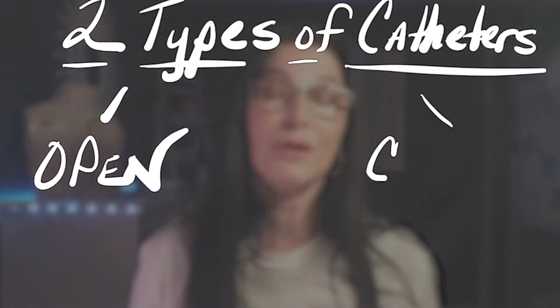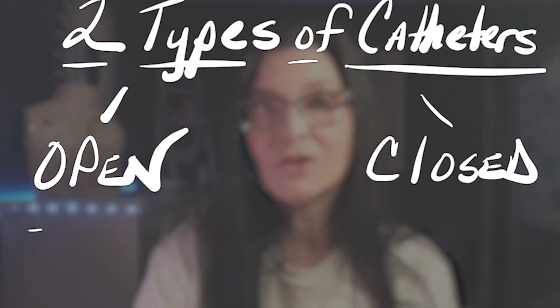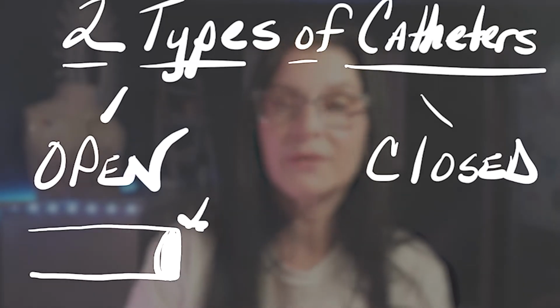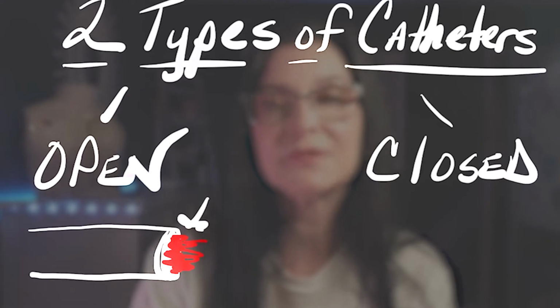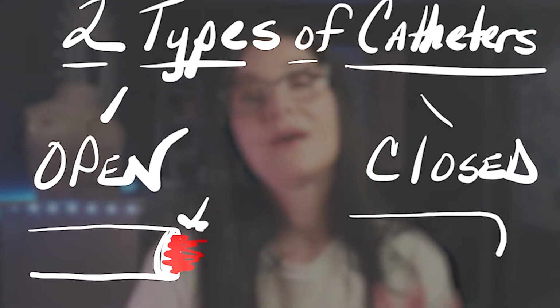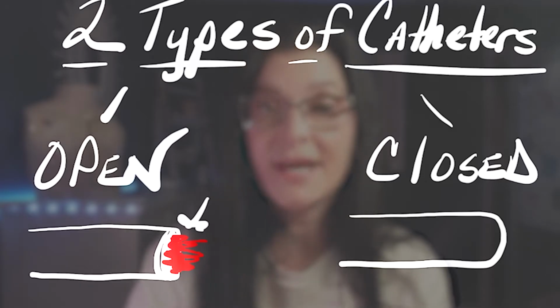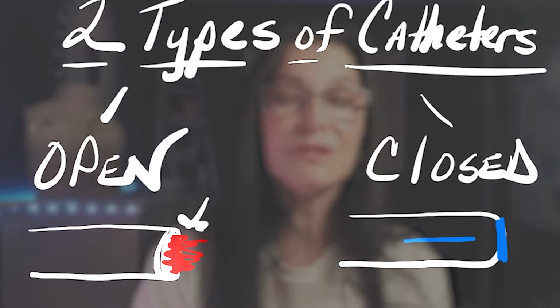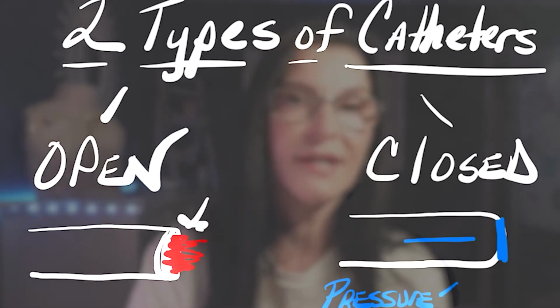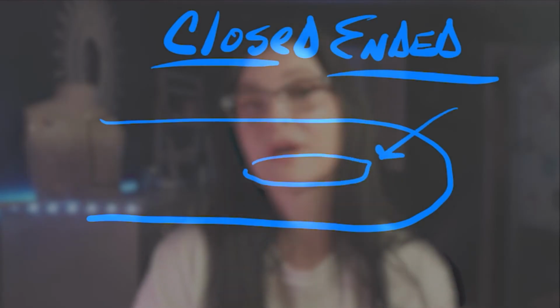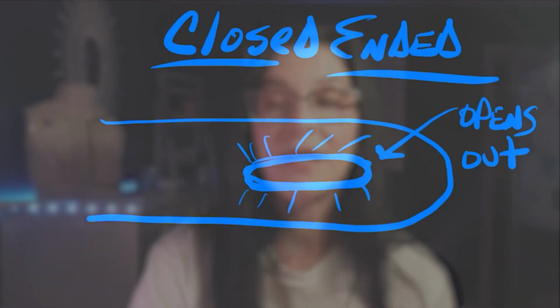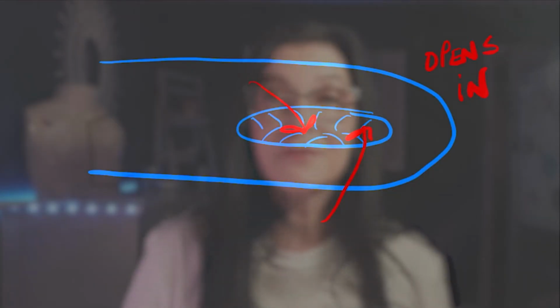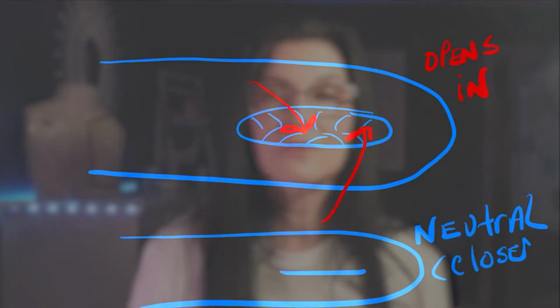So 2 major categories that all central venous catheters fall into, ports included, is that they can be open or closed-ended. An open-ended catheter looks like the end of a drinking straw. Blood will sit here and it's more susceptible to clotting because of that. A closed-ended catheter has a dead end with a built-in valve mechanism, which is usually a split along the side that's pressure activated. So the valve opens out with positive pressure, such as with an infusion or with flushing, and conversely, it'll pull in on itself with negative pressure, allowing for the aspiration of blood. Without either of these, it remains closed or neutral.